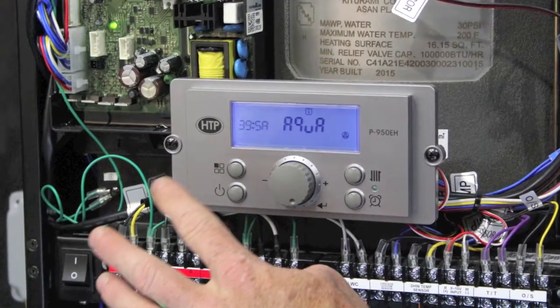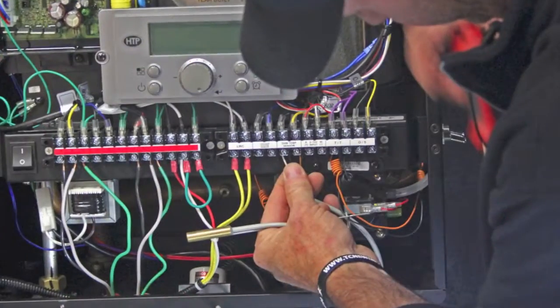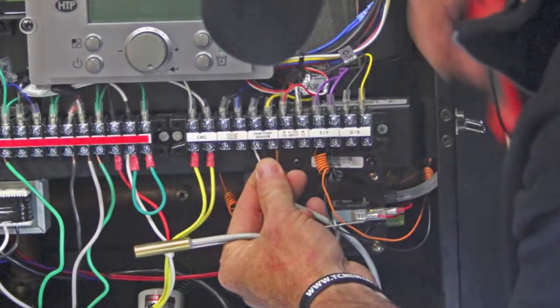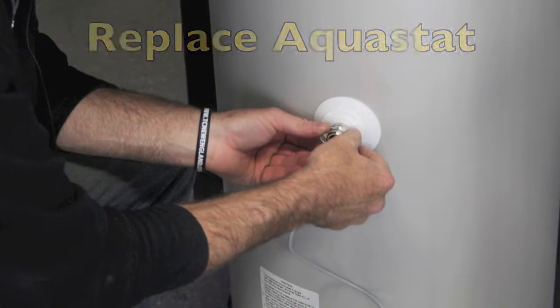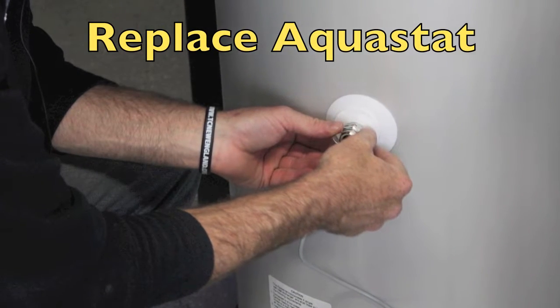If Aquastat is selected in installer mode parameter 39, then ensure proper wiring connections to the designated terminals on the low voltage terminal strip. Ensure proper connections at the Aquastat. After proper connections have been verified, replace the Aquastat.